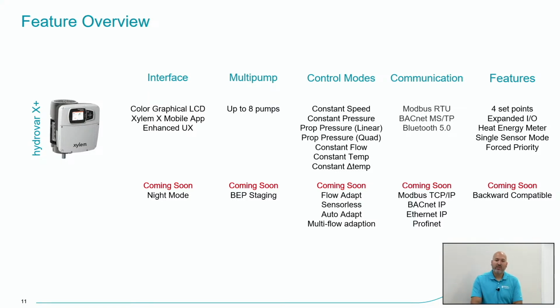For communication protocols, built in as standard to each unit, we are going to have Modbus RTU and BACnet MSTP available in every single unit. However, there is a port where you can add an additional module. It's an Anybus module, which basically has any protocol you can think of, so if you need something different, we would just require you to purchase that additional module and install it in the field. However, the majority of applications use Modbus RTU and BACnet MSTP, which are pre-built in or standard with each unit.